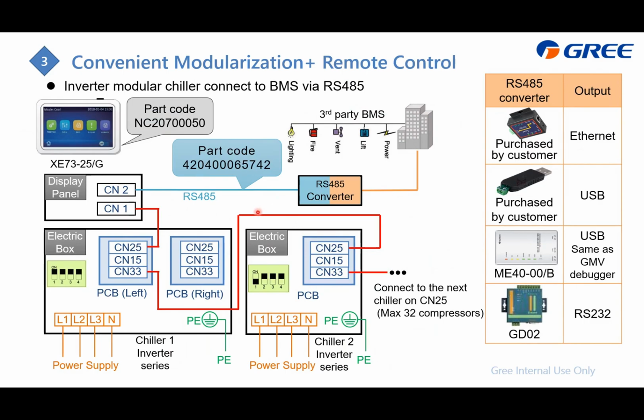This slide displays how to do the wiring from the chiller system to the PC. In this case, this is actually our latest modular chiller. We have two compressors, so we have two PCBs, and you can do the wiring from this CN25 to the left side PCB's CN33, and then from this CN25 to this one. And from here, the output you can take from this CN2. Then through the RS485 converter, we need to change it to the signal for the PC, which is for the BMS system.